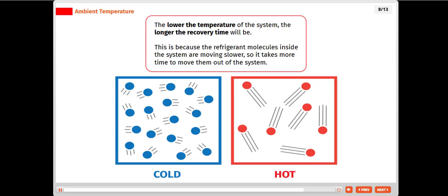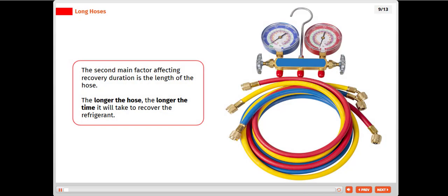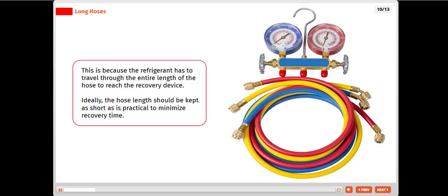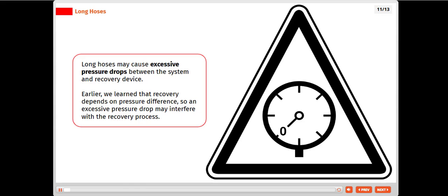The second main factor affecting recovery duration is the length of the hose. The longer the hose, the longer the time it will take to recover the refrigerant. This is because the refrigerant has to travel through the entire length of the hose to reach the recovery device. Ideally, the hose length should be kept as short as is practical to minimize recovery time. Long hoses may cause excessive pressure drops between the system and recovery device. Earlier, we learned that recovery depends on pressure difference, so an excessive pressure drop may interfere with the recovery process.